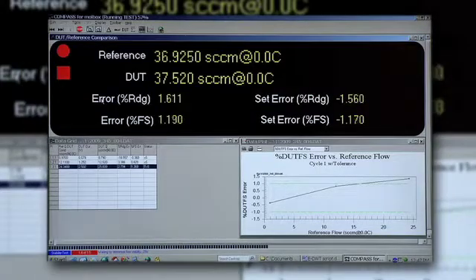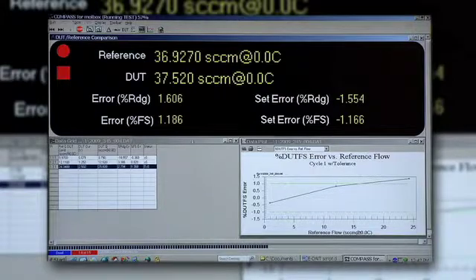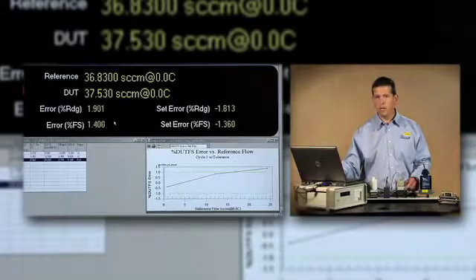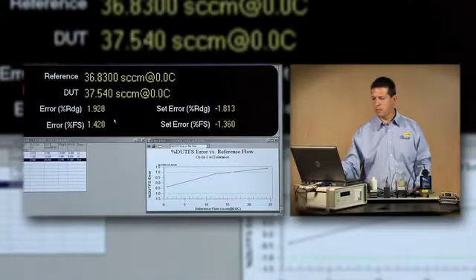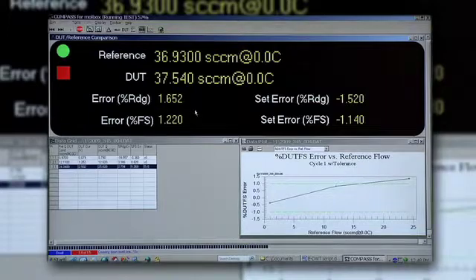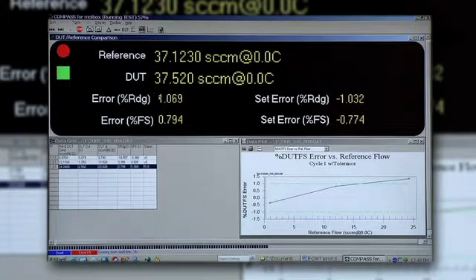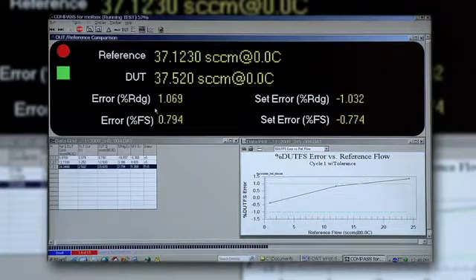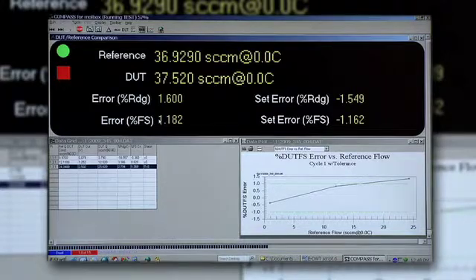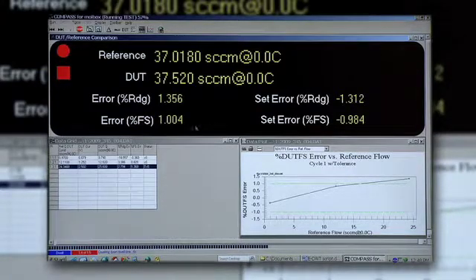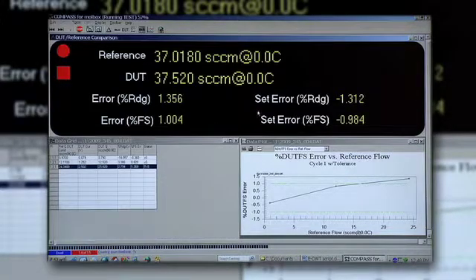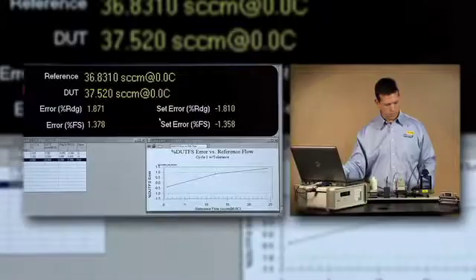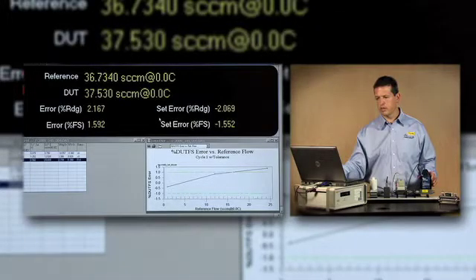Now returning over to our test, you can see that both the reference indication, which is coming from the molbloc and molbox measurement, and the device under test measurement are shown. You have error calculations shown in both percent of reading and percent full scale. And note that we have both an error and a set error indicated on the screen.